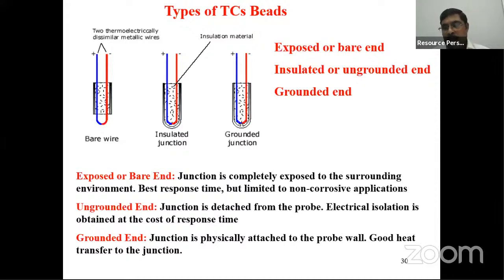Rapid sensing: if the bead is exposed to the environment, because of the better heat transfer characteristics, it will give rapid sensing. Sometimes, because of chemical hazards and other operational issues, you may need to protect the bead. Therefore, you need to have an insulation. That is the insulated junction. Mostly the insulated junction thermocouple is used in furnaces, because furnaces experience high temperature and there will be a lot of flue gas and ash and many other things. Therefore, you need to protect it. So based on your sensing requirement, you can opt for either a bare-ended thermocouple, an insulation-ended thermocouple or a grounded thermocouple.